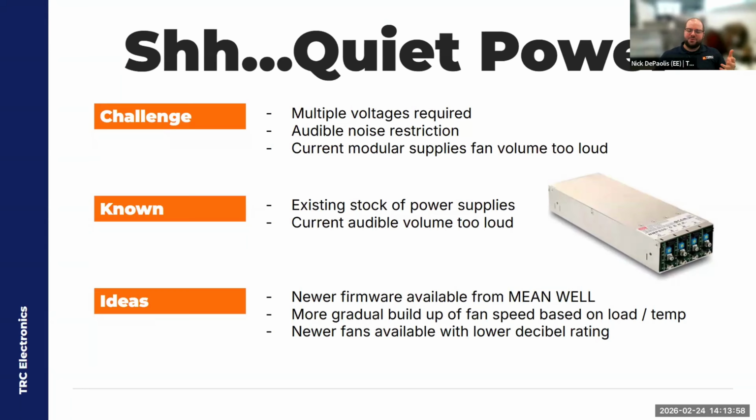Now, the issue they had is there was no ability on their end to redesign or replace the power supply platform, and they were kind of stuck with this Mean Well NMP series. So what we had to do essentially was to see, okay, what options do we have to reduce the noise without requiring recertification of the system, without taking down their systems themselves and causing massive service outages.